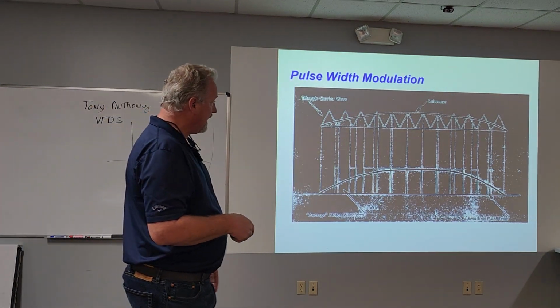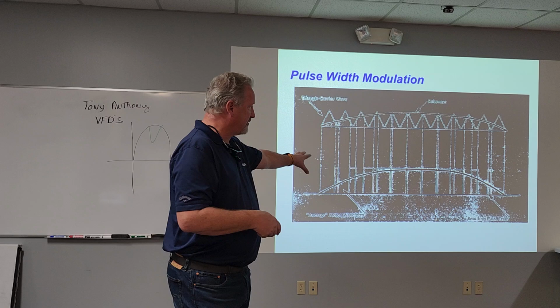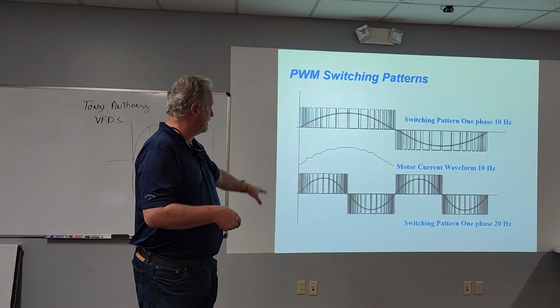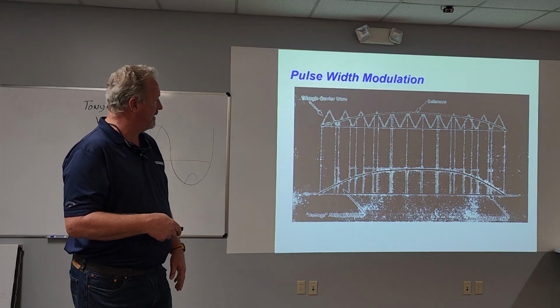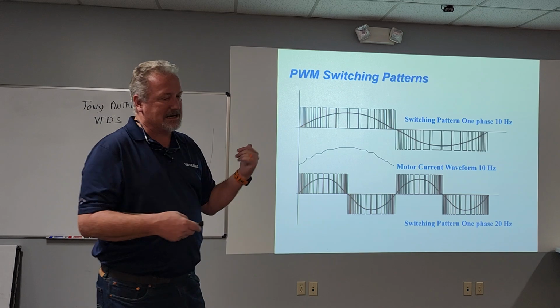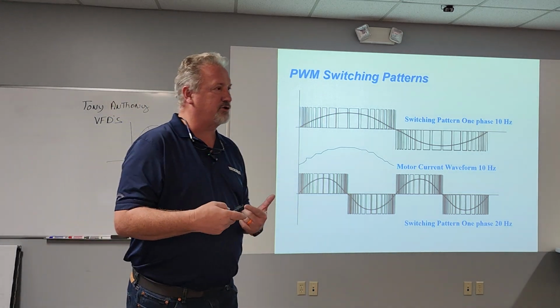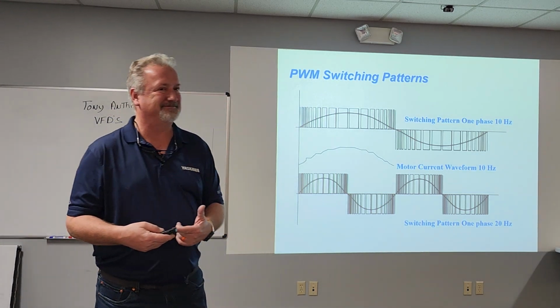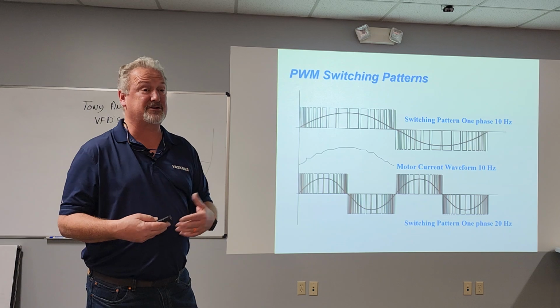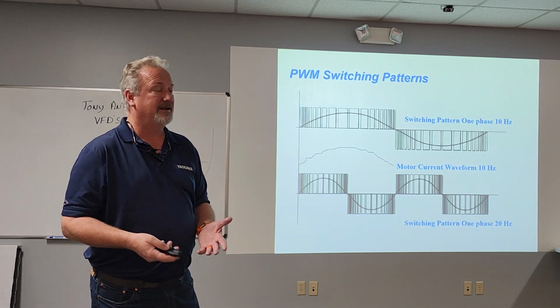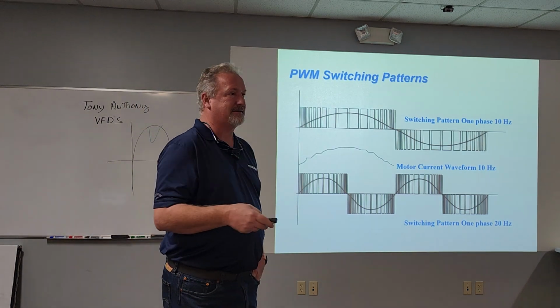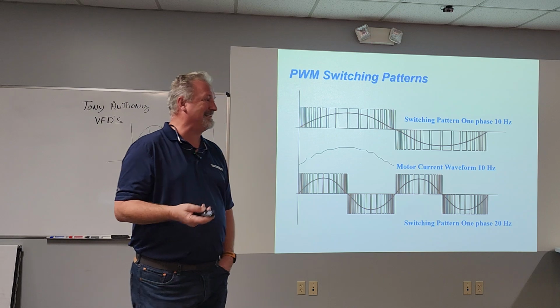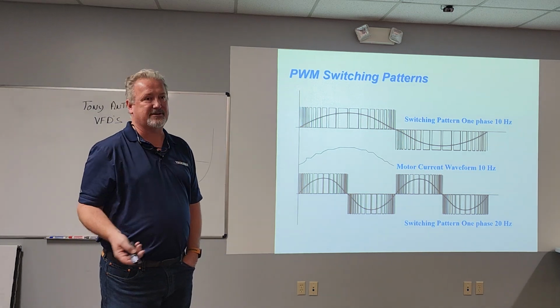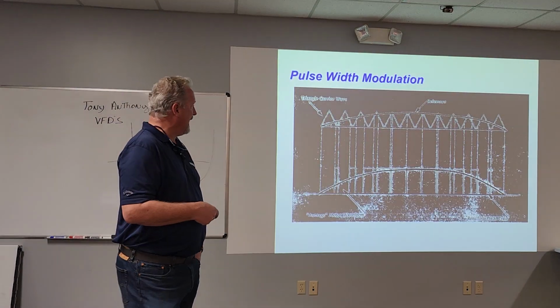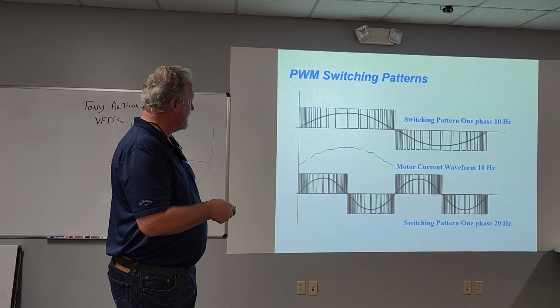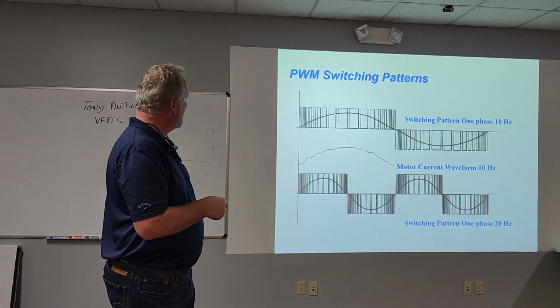Now, this is why it's so important. Hopefully, here we go. This is a little prettier. This is why it's so important, though, to make sure you've got the right motor for a drive. You know, we always say you want to make sure you have an inverter-rated motor. The reason is we're not putting AC out to that motor. We're putting a pulse DC that simulates AC to the motor. The thing about these pulses, you see how high they are?